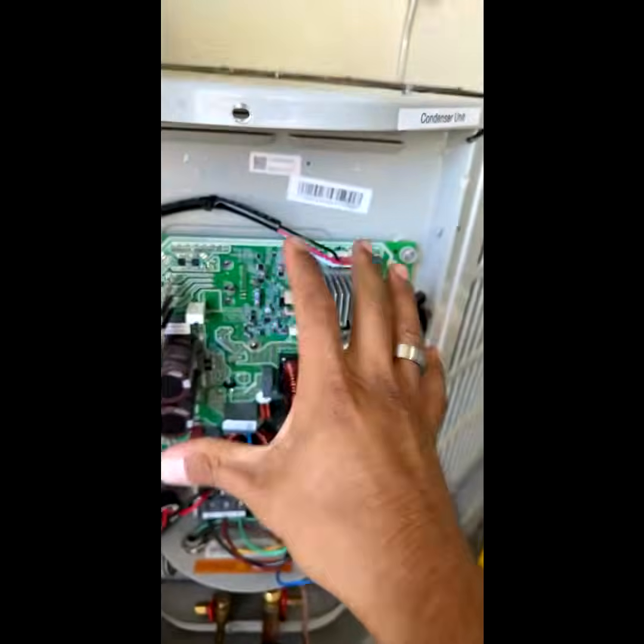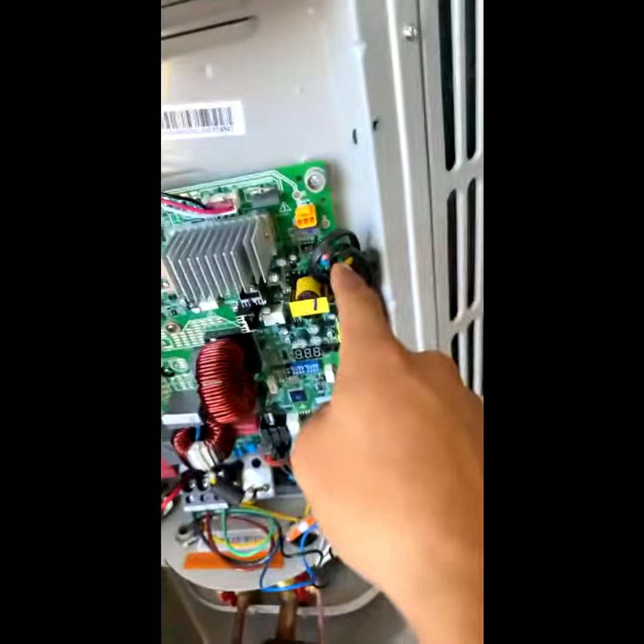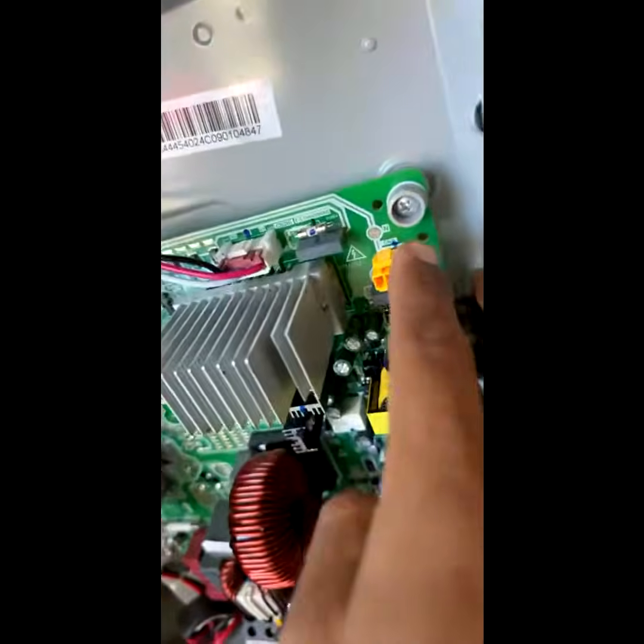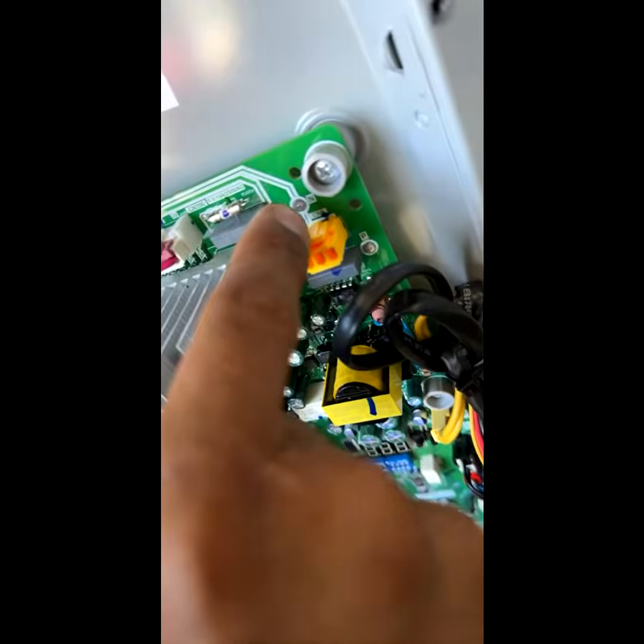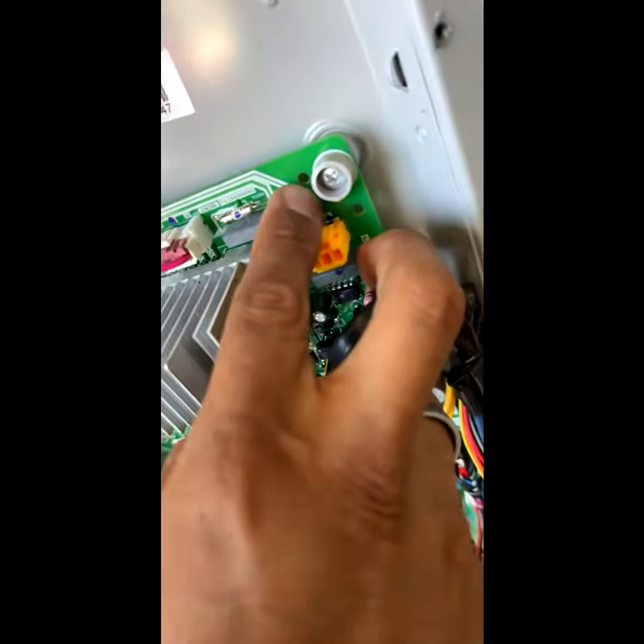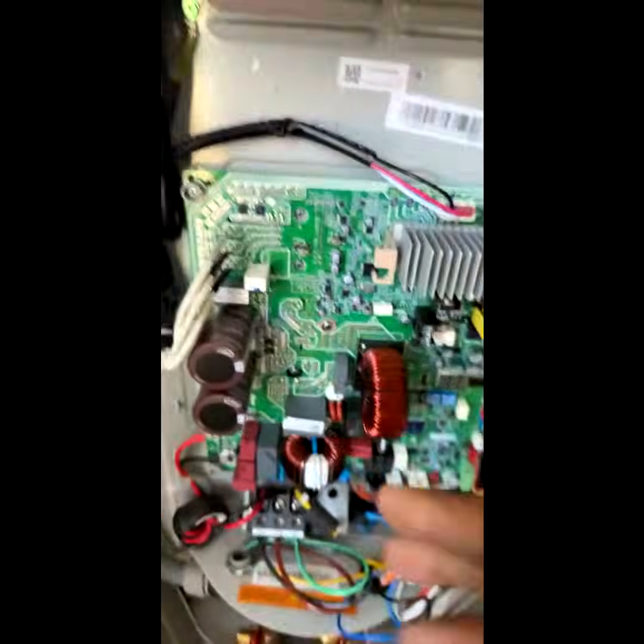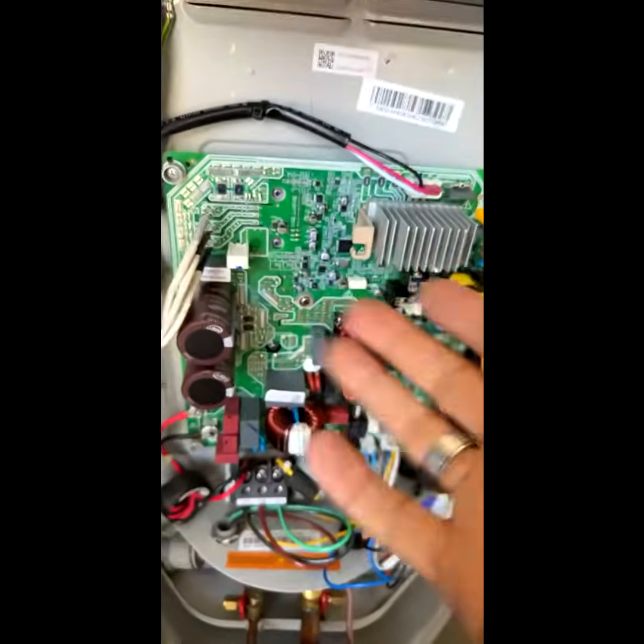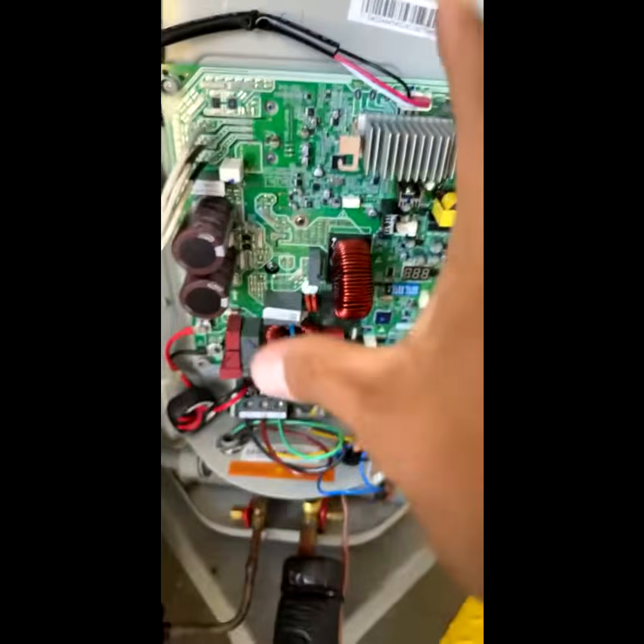Then you can safely touch it, because even when you turn off the disconnect, it still has to discharge on its own, and you've got to wait a couple of minutes. But you confirm by checking that little circle there and that one there. Once it hits below 45, then you can start to touch this, if you have to unplug or work on something. But these are inverters.